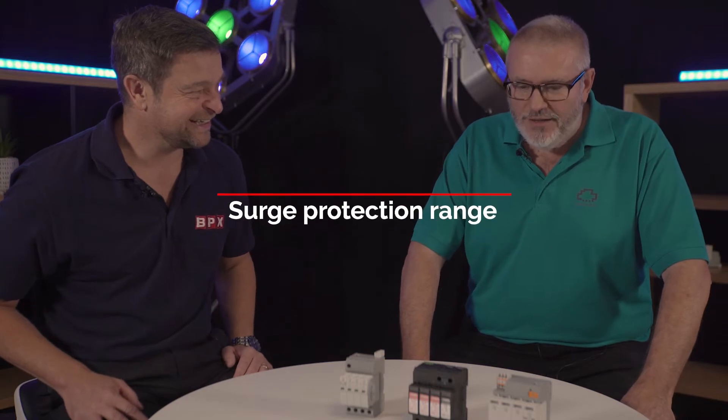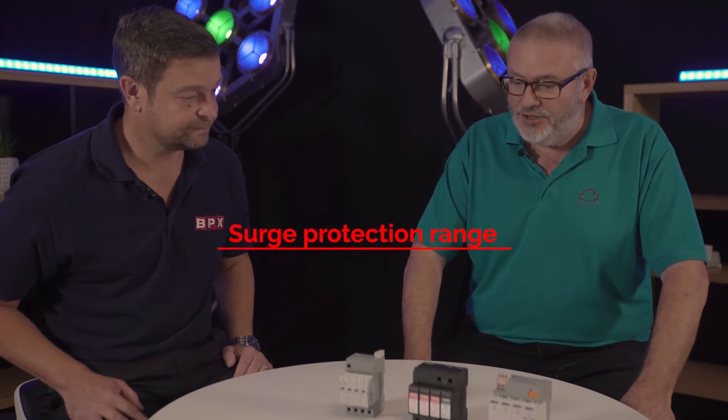Please explain a little bit about surge protection and its functionality. They protect the loads they're connected to in front of by diverting a current away to earth, so the load only sees the nominal current. If you have an electrical switching event, that could generate up to 2000 amps in a panel, and the SPD will divert most of that 2000 amps to earth.